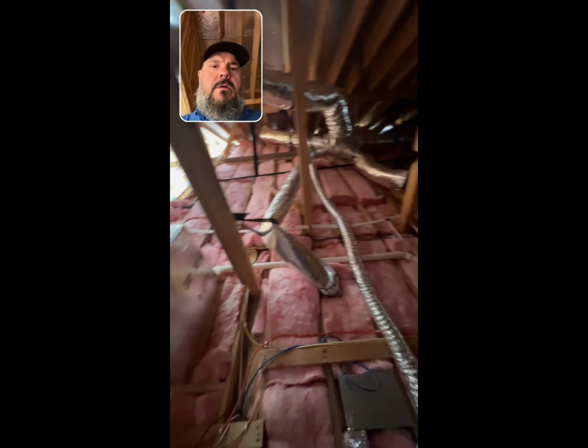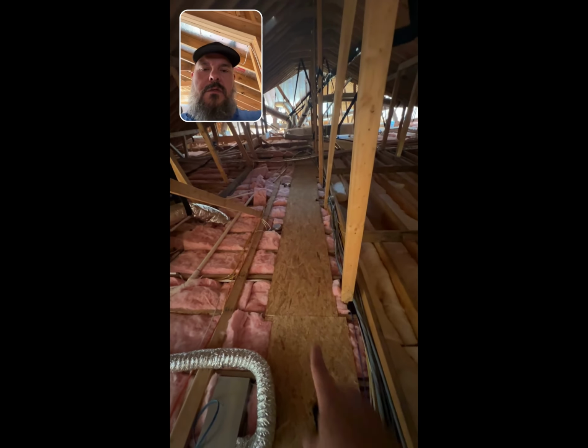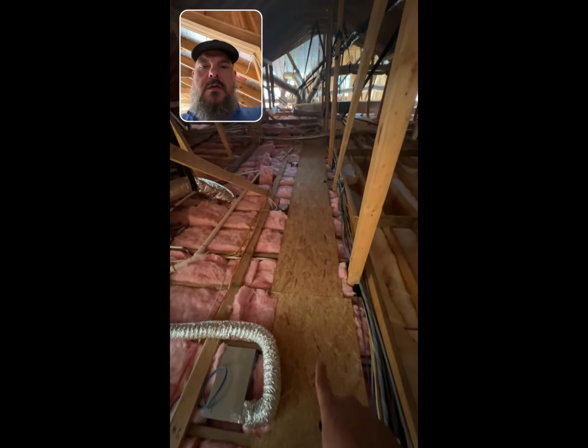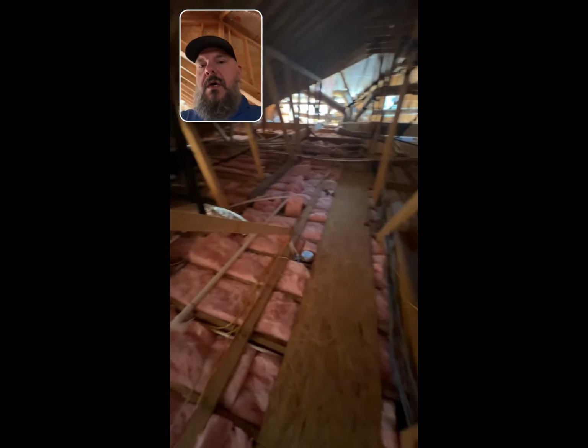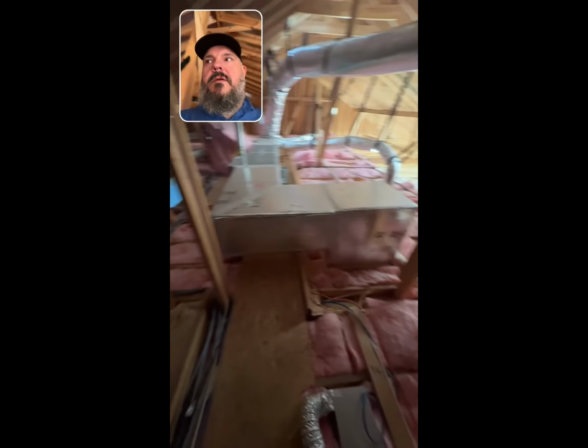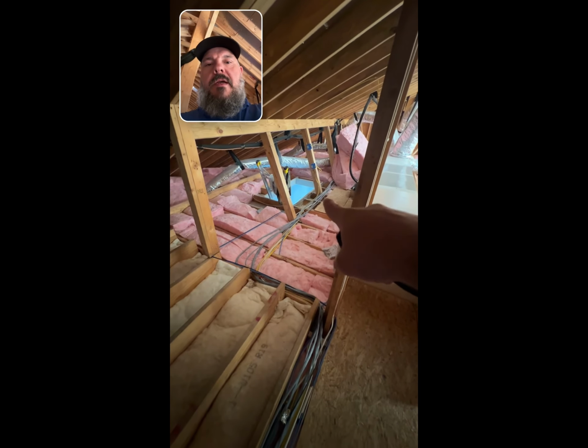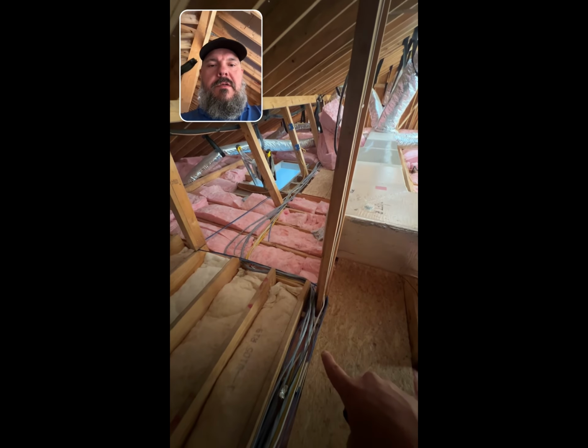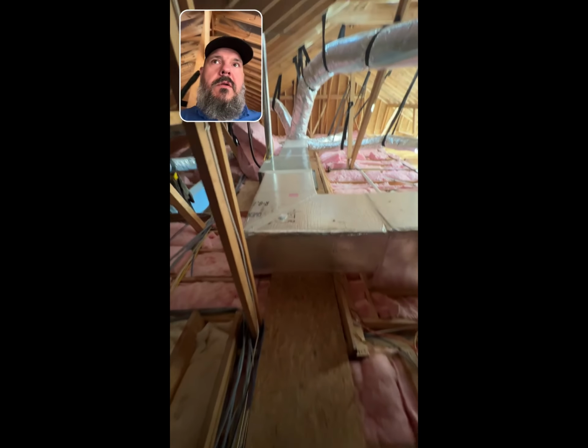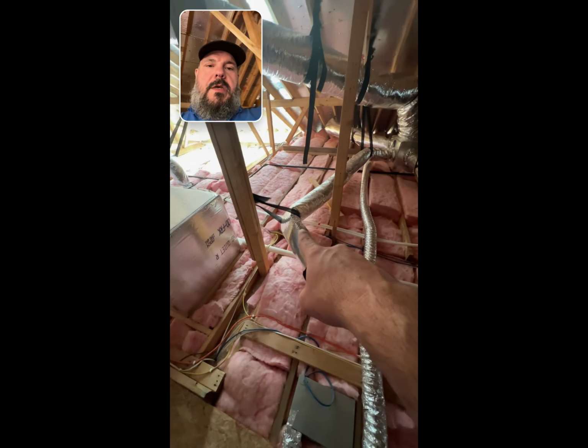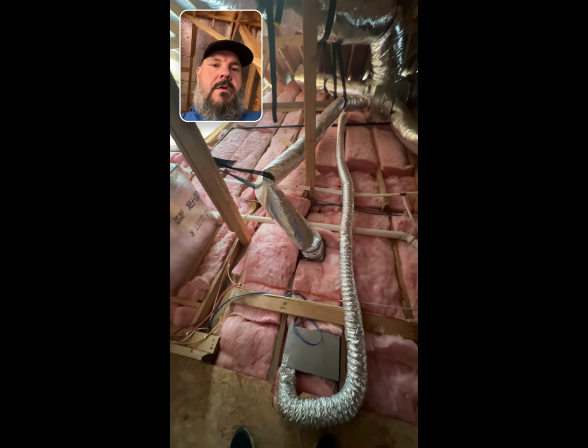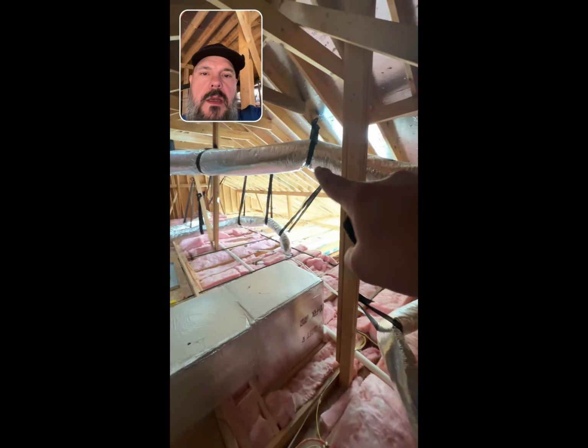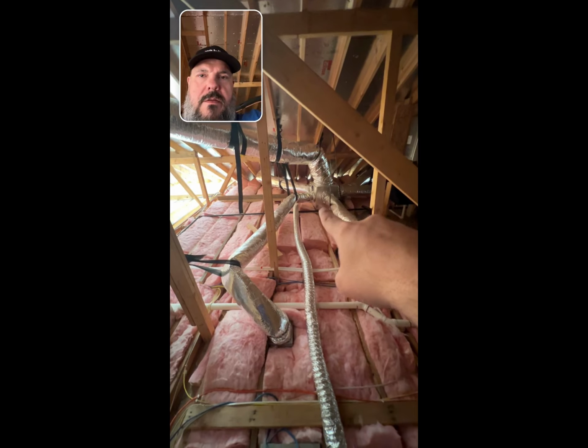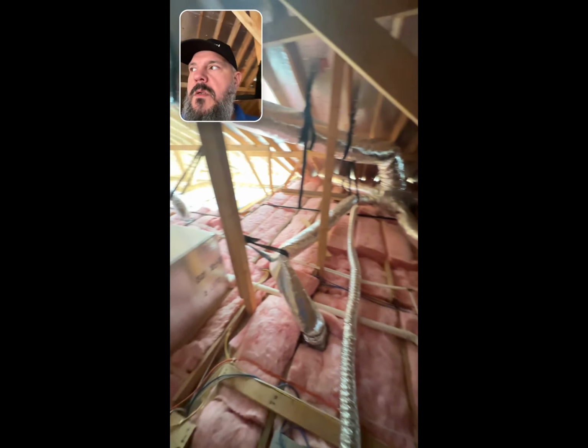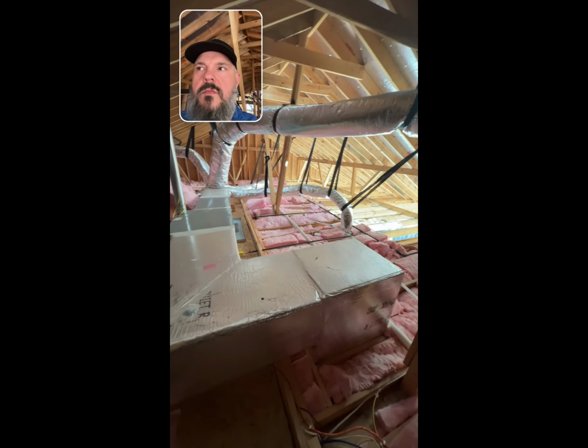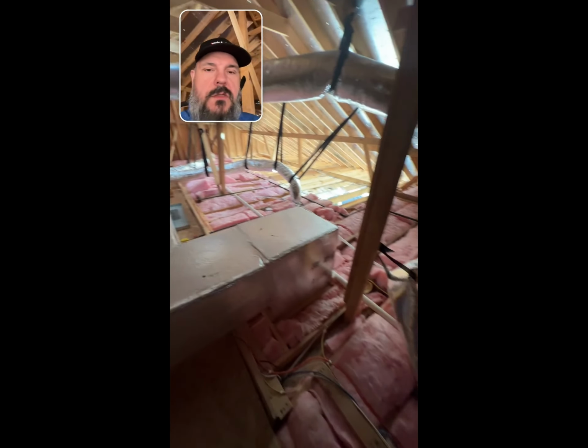because we have all of this. So this is my catwalk that is completely blocked off from my attic access. Okay, so come up the attic ladder, and I have to walk across ceiling joists, wires, and all that to get to my catwalk. As you can see, we have flex ductwork kinked off. We have supply airs coming to pressure boxes with a spaghetti explosion coming off of them. So there's no trunk line, branches, or any of that. It's just a spaghetti explosion of flexible ductwork.